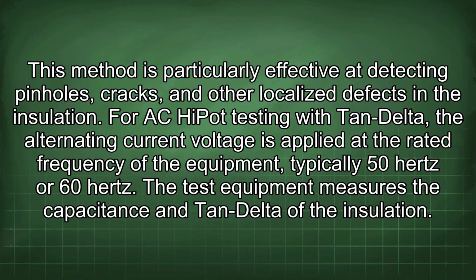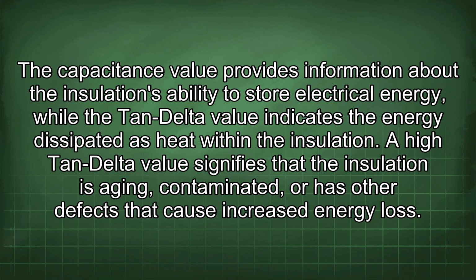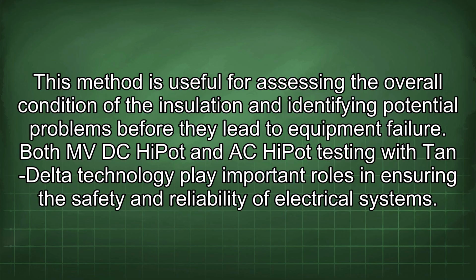For AC HiPot testing with tan delta, the alternating current voltage is applied at the rated frequency of the equipment, typically 50 Hz or 60 Hz. The test equipment measures the capacitance and tan delta of the insulation. The capacitance value provides information about the insulation's ability to store electrical energy, while the tan delta value indicates the energy dissipated as heat within the insulation. A high tan delta value signifies that the insulation is aging, contaminated, or has other defects that cause increased energy loss.